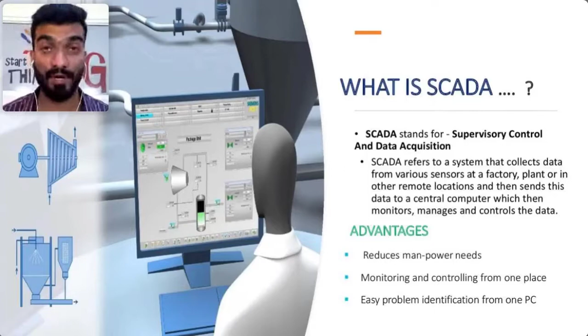The advantages: it reduces manpower because the entire plant can be controlled from one place. If you know about cement plants or power plants, there is a control room where all these SCADA systems are located. They can control the entire plant through this SCADA, monitor it, see the trends, see where something goes wrong and what the error was. SCADA helps give this information. So it reduces manpower, is used for monitoring and controlling from one place, and allows easy problem identification from one PC, one place.